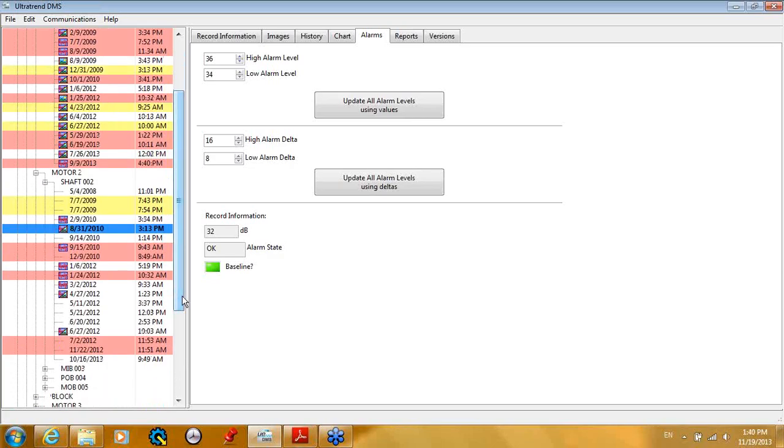I do actually have one customer that I know pretty well that's been collecting data for probably close to 8-9 years. They've collected so much data that they're at a point now that if they use the same bearing and the same motors, they can look at their history and know when that bearing is going to fail, when they do their lubrication correctly.